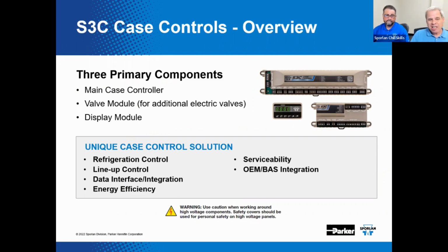The S3C was designed to facilitate both installation and integration by the refrigerated appliance OEMs. That's a fancy way of saying, the refrigerated case manufacturers and other devices of that ilk. It is also compatible with retrofit applications in existing supermarket refrigeration control installations. Now, when properly set up, the S3C provides automated configuration and network integration. It can provide that standalone feature we talked about, or BAS coordinated control of up to a maximum of 8 refrigerated cases per lineup. And what else can it do, John?